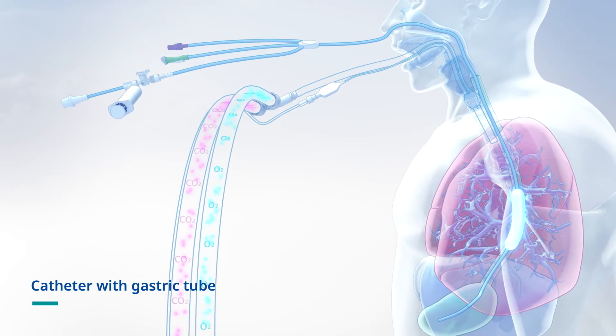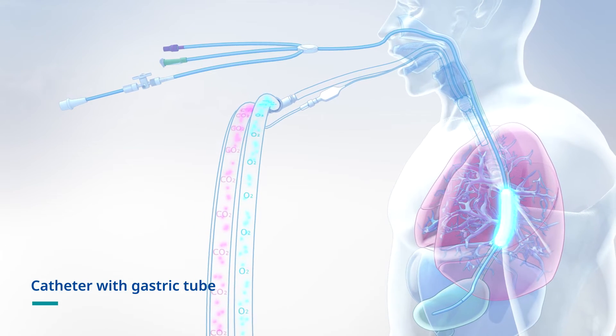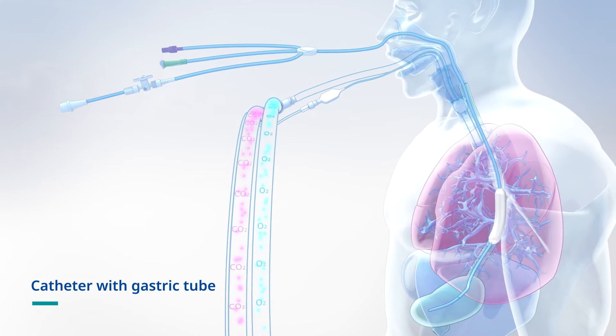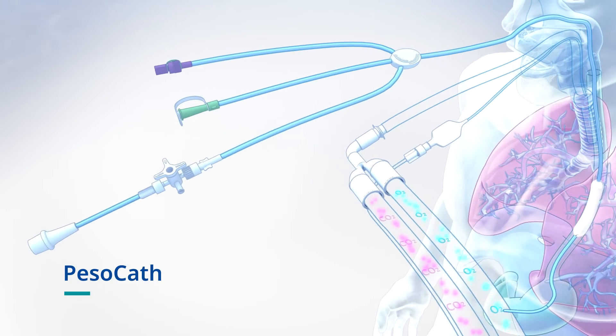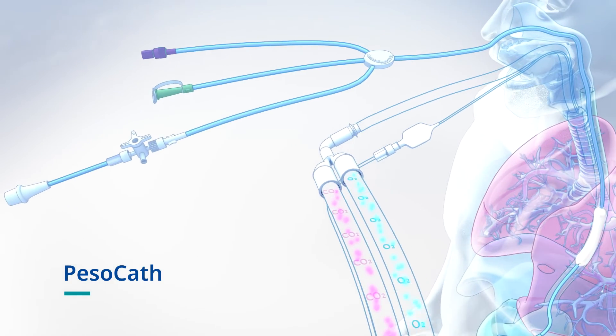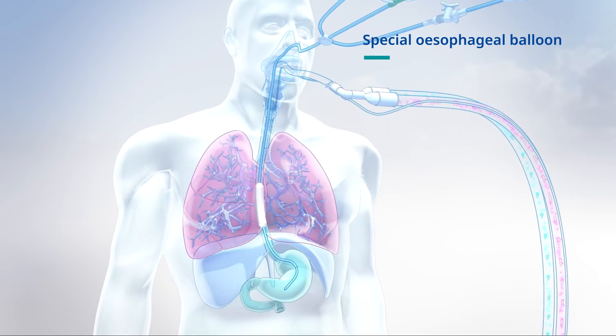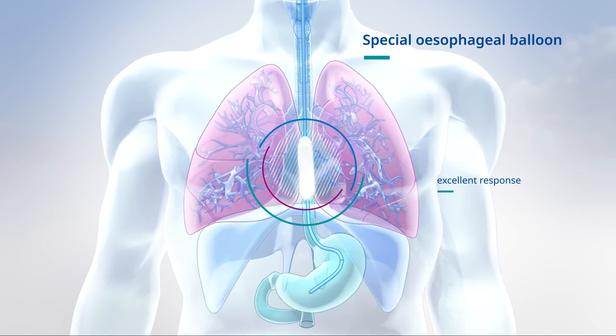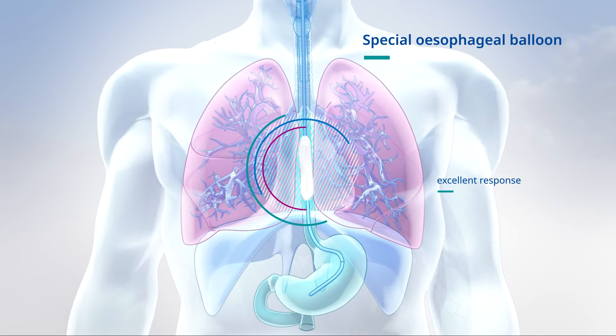The first available catheters often resulted in compromise and were less suitable for prompt pressure transmission. Löwenstein's PesoCath was specially developed for esophageal and transpulmonary pressure monitoring. Its specially designed esophageal balloon facilitates an excellent response to rapid pressure changes under ventilation and is designed for the dynamic requirements of transpulmonary pressure measurement.